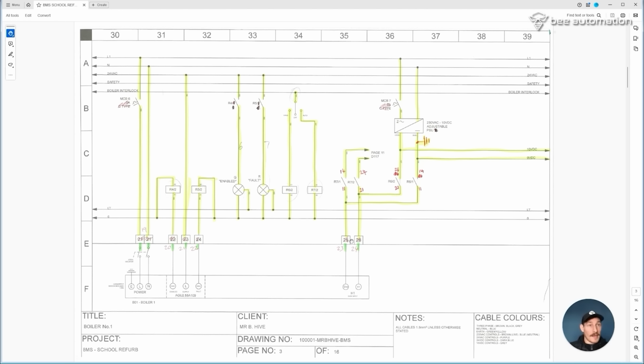So that's the terminal blocks all updated throughout, and the relay pole numbers updated throughout. Next, on page 3, I'm going to add numbers which tell you which part of the relay these cables are going into - it got a bit confusing when wiring it, so it's best practice to add those in, showing the common, normally open, or normally closed terminals. You can see it visually, but let's do things properly and add the actual identification of the relay terminals.